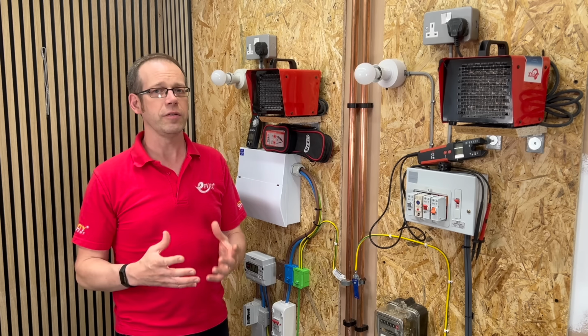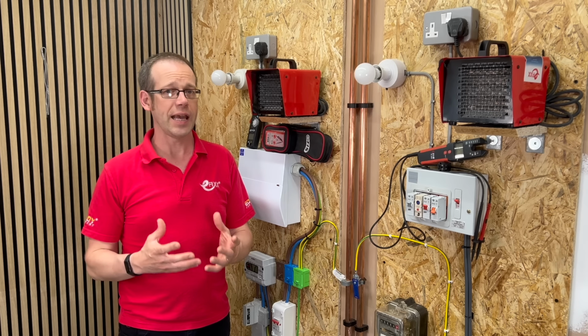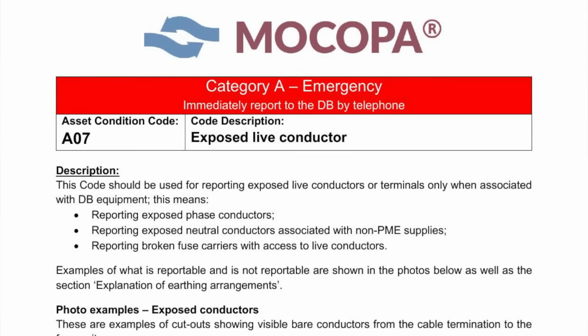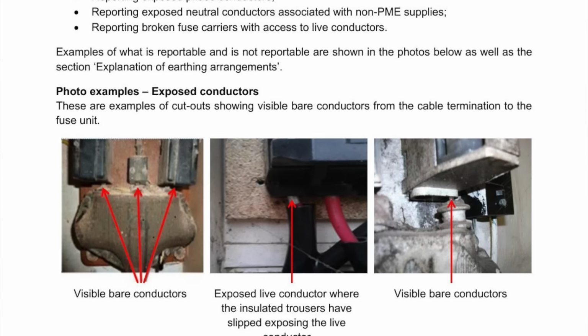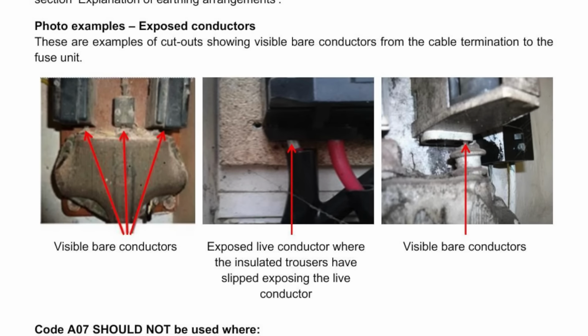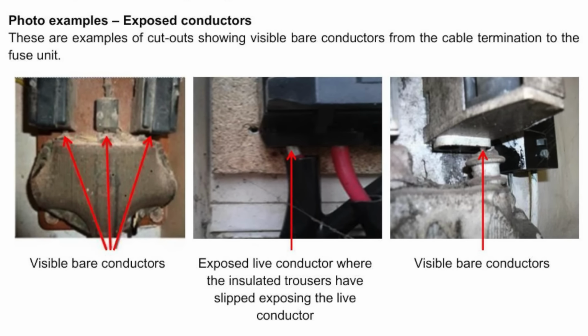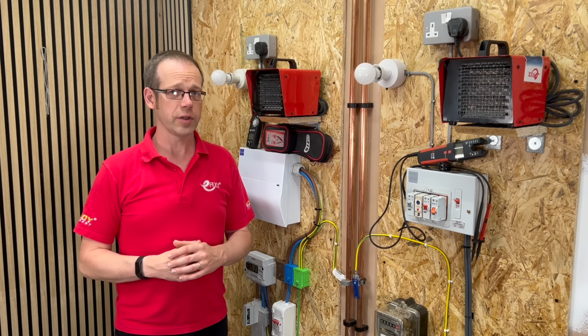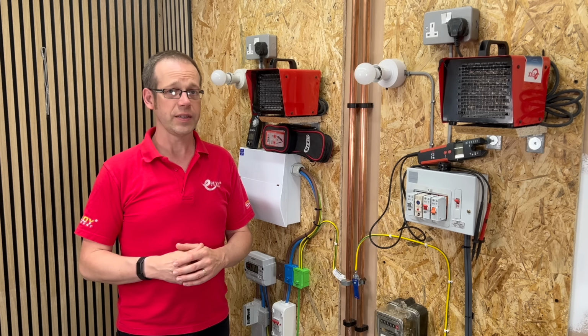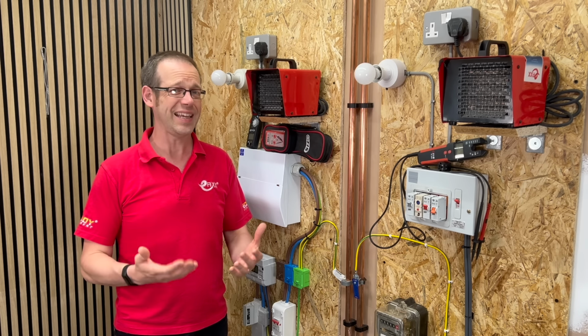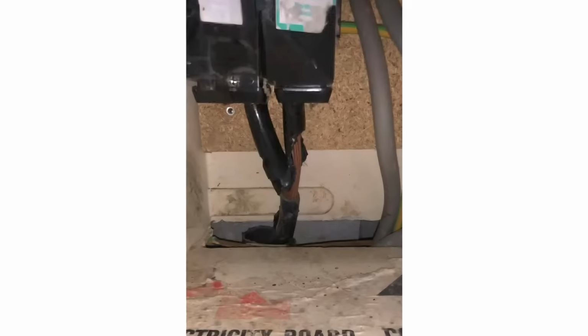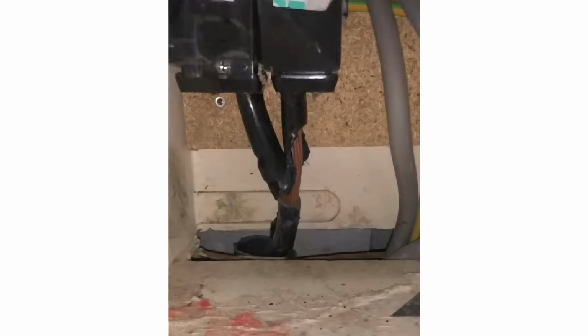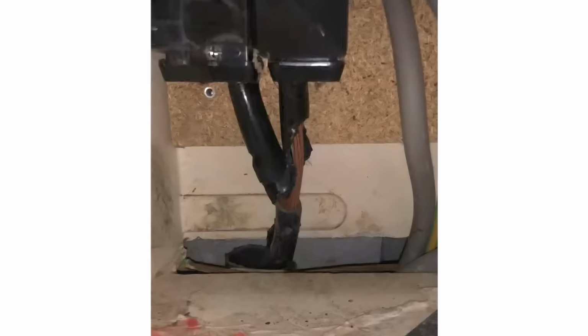The cable insulation feeding into service heads is also susceptible to age-related degradation. The most common issues include cracking or splitting of the outer sheath, loss of mechanical strength and shrinkage, which exposes conductive elements. In older installations using vulcanized rubber or cloth-based insulation, deterioration is often accelerated by heat and mechanical stress. Exposed conductors can create the risk of electric shock, particularly in damp environments or where conductive dust is present.